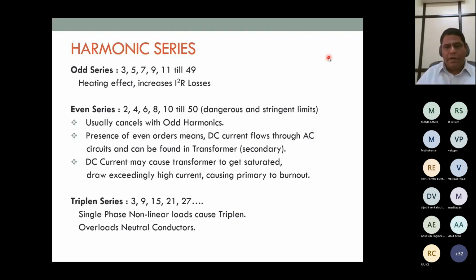There will be DC current. A presence of even series means there will be DC current in the circuit, which is mostly due to faulty rectifiers or defective diodes in the circuits. The triplen series is mostly due to single phase nonlinear loads like our computers or other single phase machines, which usually overload the neutral conductors. Neutral conductors are slightly reduced in size, as we use in general, but if those conductors are overloaded, that may be because of only the triplen series.